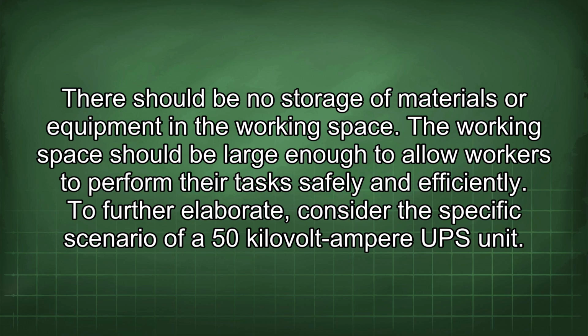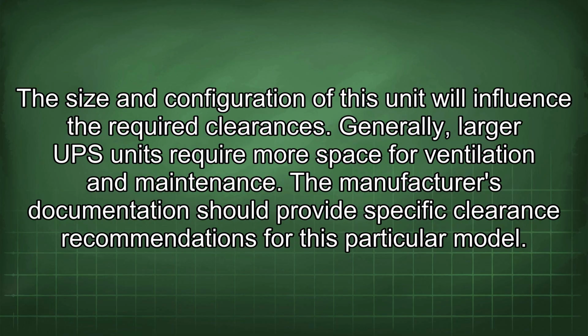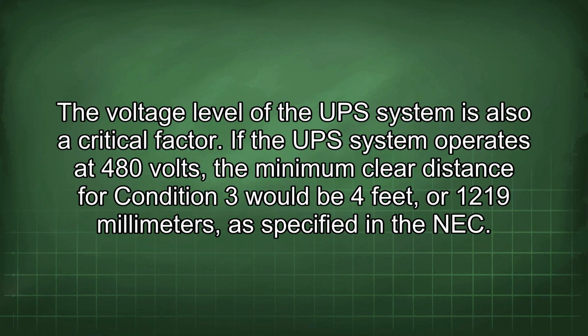To further elaborate, consider the specific scenario of a 50 kilovolt-ampere UPS unit. The size and configuration of this unit will influence the required clearances. Generally, larger UPS units require more space for ventilation and maintenance. The manufacturer's documentation should provide specific clearance recommendations for this particular model. The voltage level of the UPS system is also a critical factor. If the UPS system operates at 480 volts, the minimum clear distance for condition 3 would be 4 feet or 1219 millimeters as specified in the NEC.